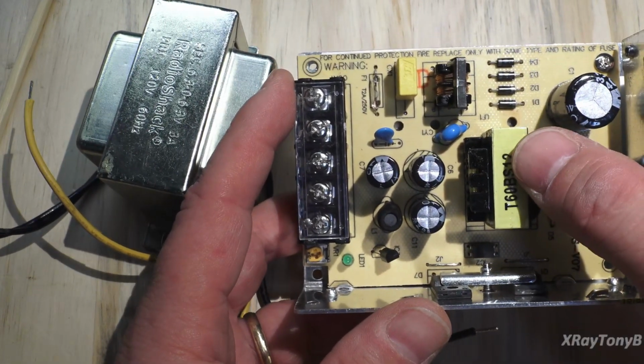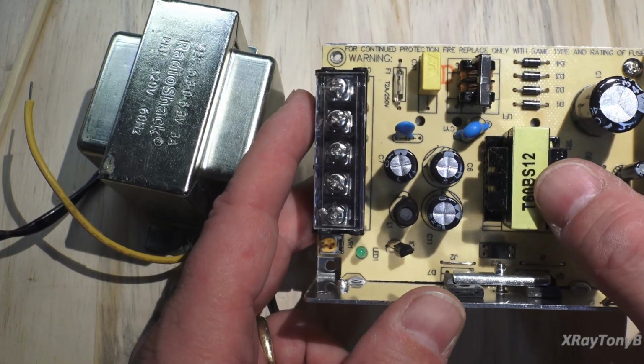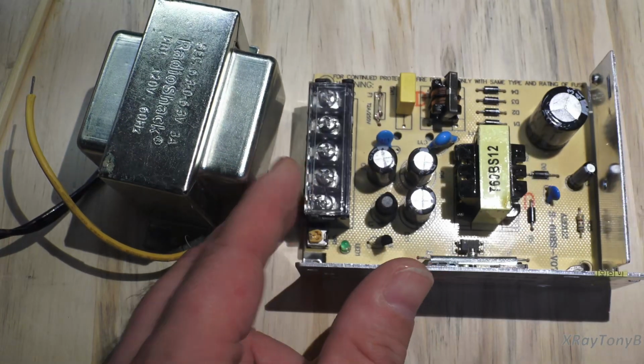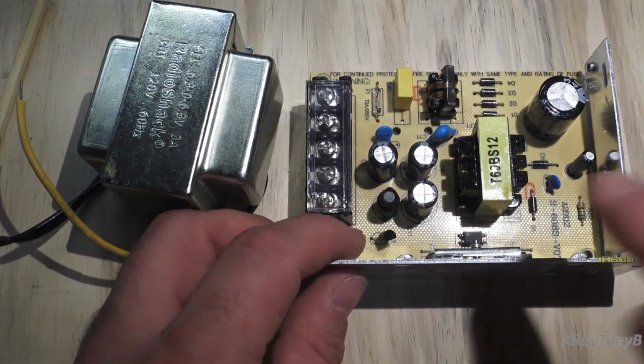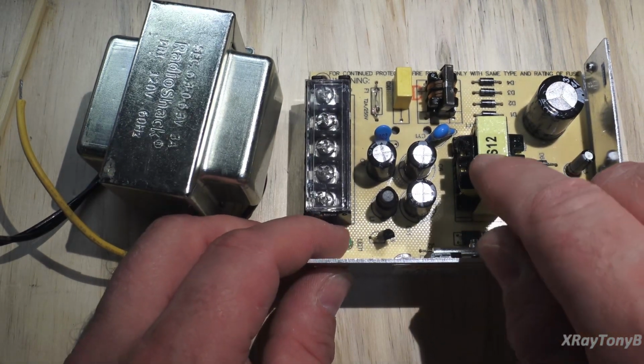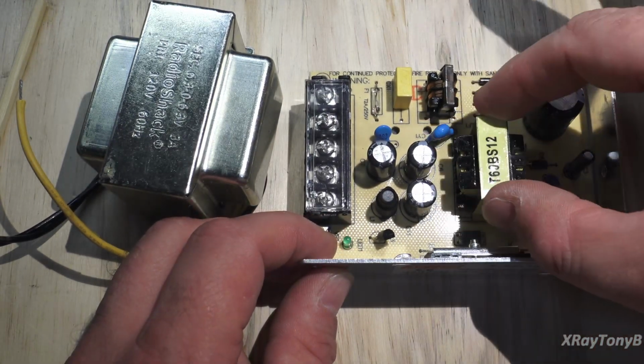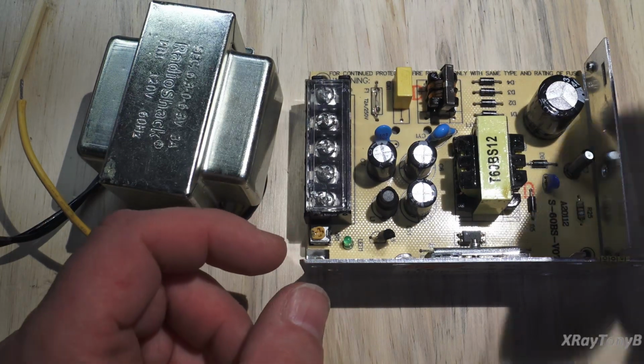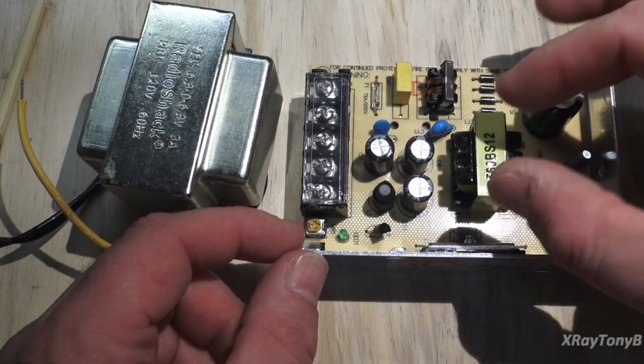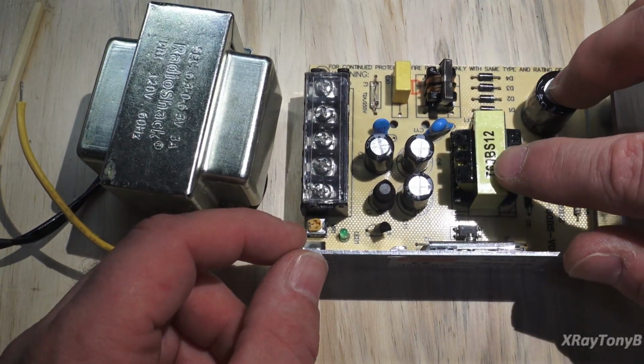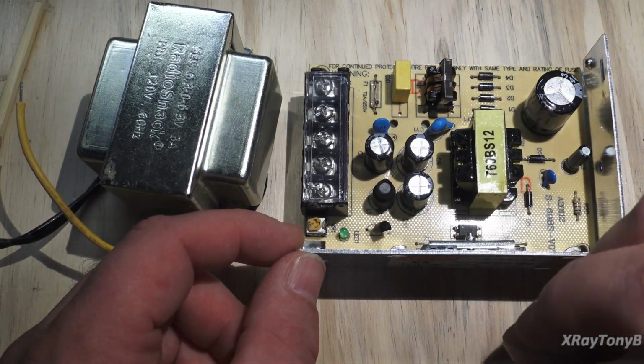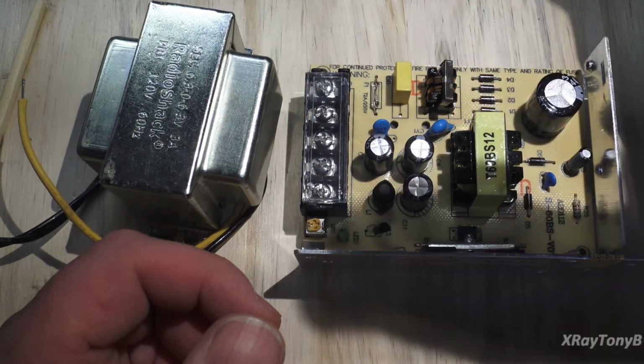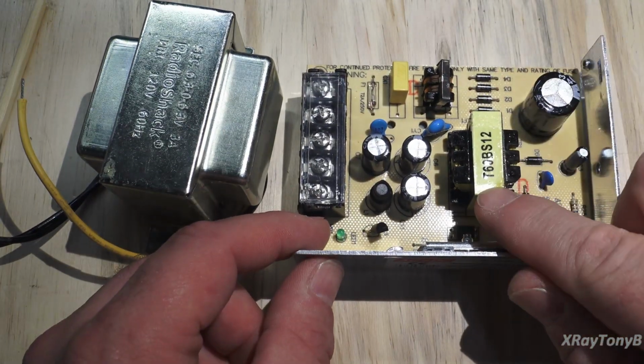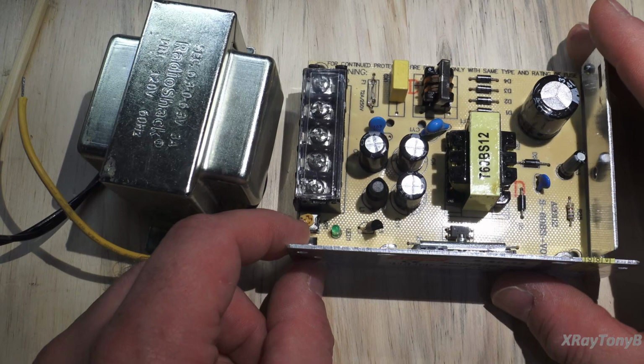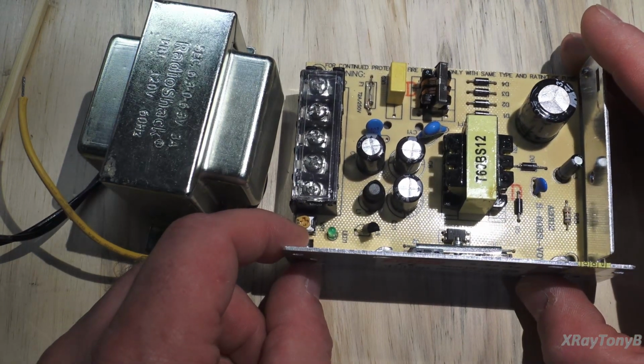It's no longer running at 60 hertz. By providing very quick, sharp pulses of voltage to the transformer, we're able to trick the core into never being on long enough to saturate. So just about the time the core is ready to collapse and the magnetic field is ready to saturate, it shuts off, and then it's given another big pulse to charge it back up.